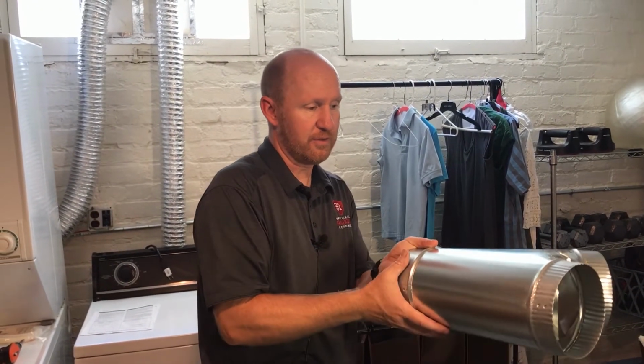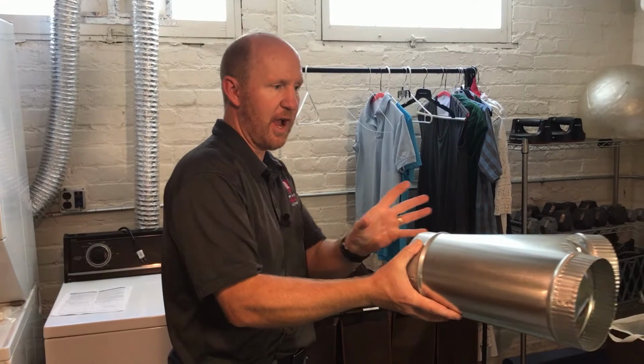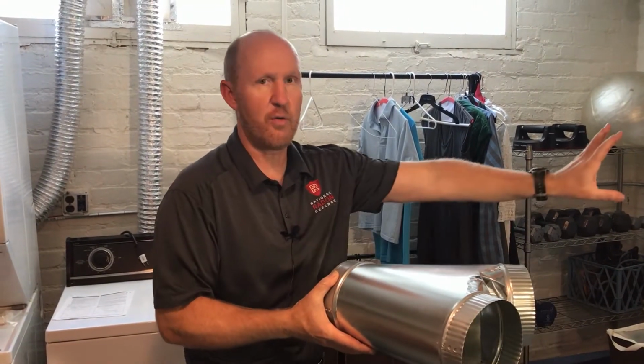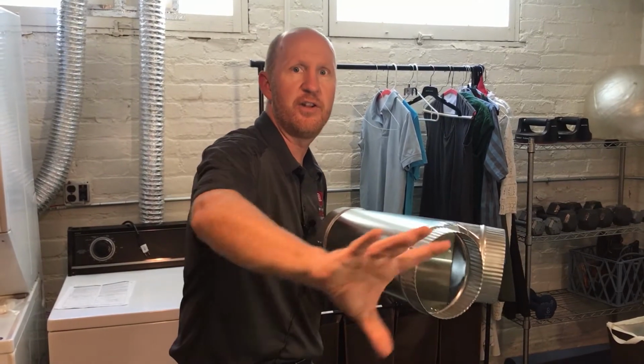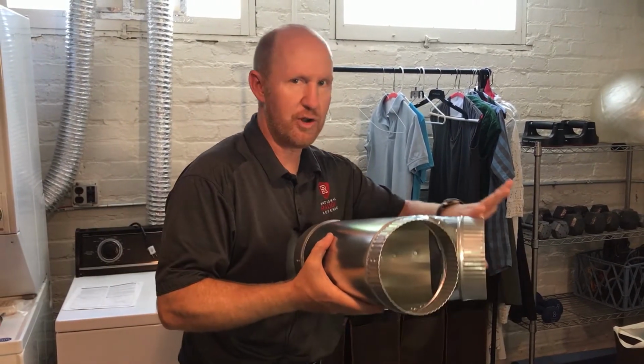Okay, when you're doing a direct vent or even a connection to an HVAC system, you may want to use this Y connector to split that fresh air coming into the house. So you split it and you go fresh air over into this room, fresh air into that room, or fresh air into the HVAC system, fresh air into the basement. You can split that using a Y or using a T fitting, okay?